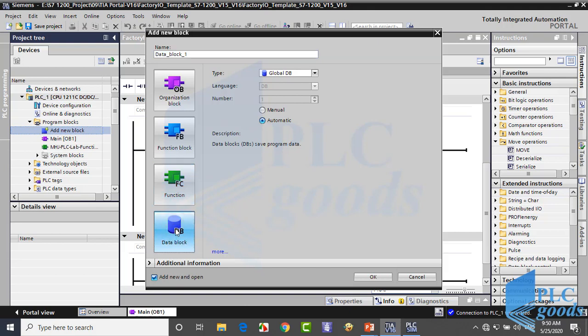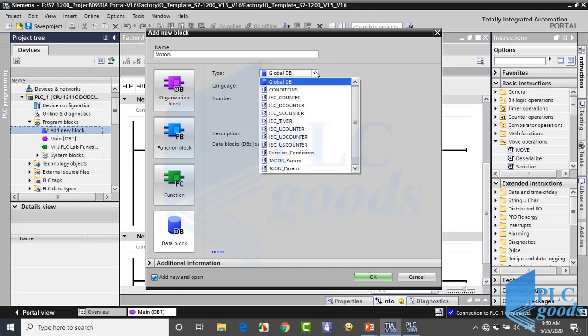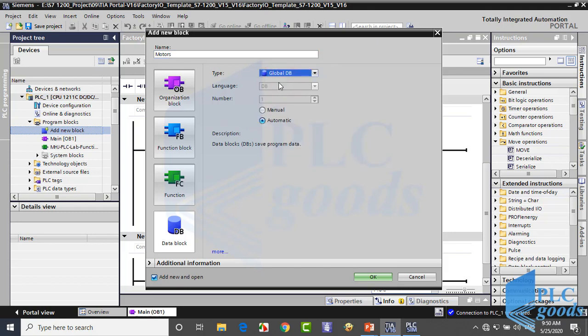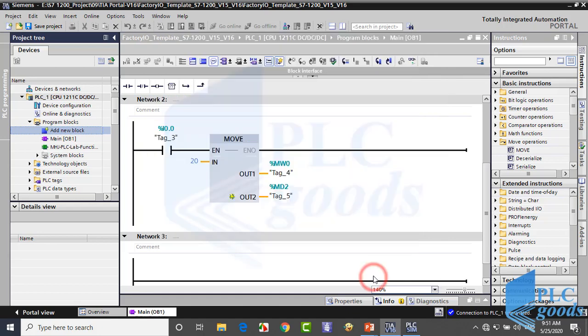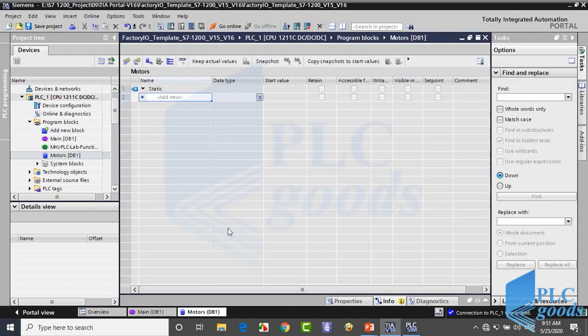A data block is a type of memory used to store data. Here define a name. Suppose there are 10 motors in an industrial process, and I need to store some initial information about them, such as their maximum, minimum, and default speeds. So I chose 'motors' as the name for this data block. Choose global DB and then click OK. My data block with the name 'motors' is inserted here.